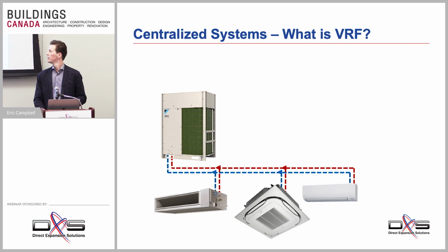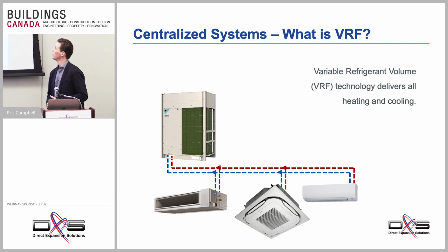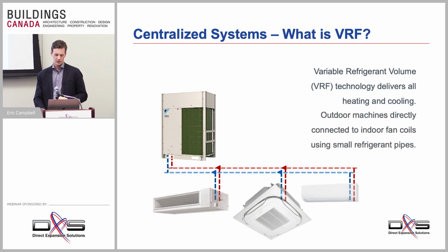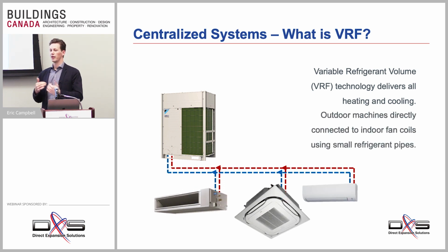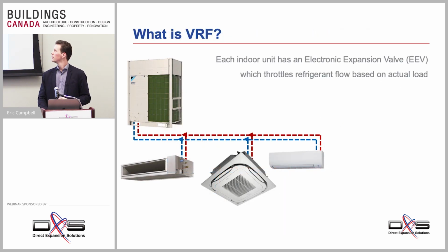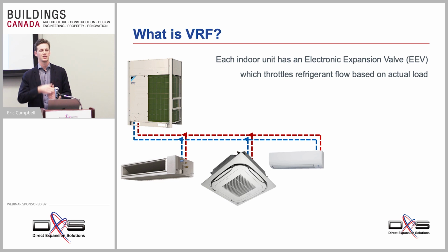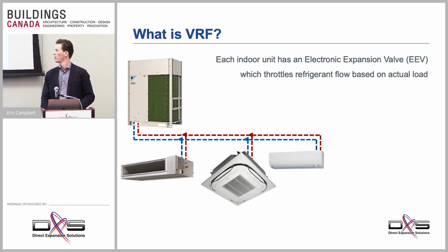So what is VRF? Like I said, we've got multiple indoor units connected to that one outdoor unit. And we transfer refrigerant around the space, and that refrigerant passing through those pipes and going into those indoor coils is what allows you to transfer the heat from the outdoor air to the indoor units in heating mode, when it's cold outside. Each indoor unit has a little expansion valve inside of it. That expansion valve meters the refrigerant passing through the coil, which, along with the inverter technology in the outdoor unit, allows you to maintain temperature in the space as evenly as possible.